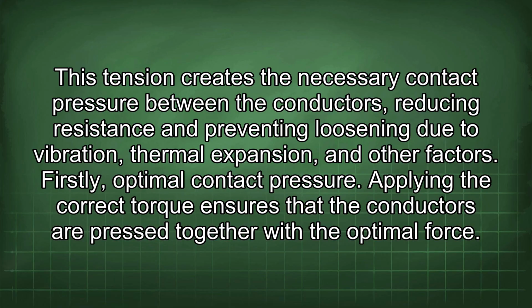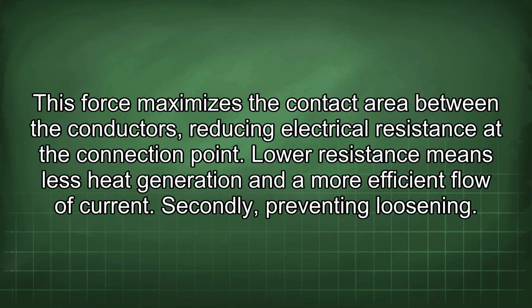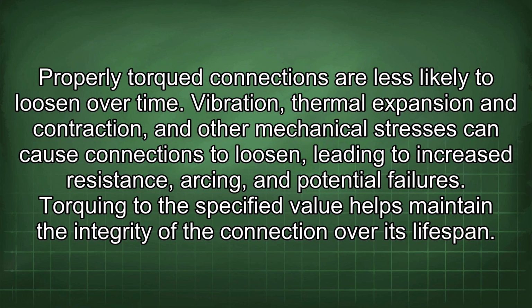Applying the correct torque ensures that the conductors are pressed together with the optimal force. This force maximizes the contact area between the conductors, reducing electrical resistance at the connection point. Lower resistance means less heat generation and a more efficient flow of current. Secondly, preventing loosening. Properly torqued connections are less likely to loosen over time. Vibration, thermal expansion and contraction, and other mechanical stresses can cause connections to loosen, leading to increased resistance, arcing, and potential failures. Torquing to the specified value helps maintain the integrity of the connection over its lifespan.